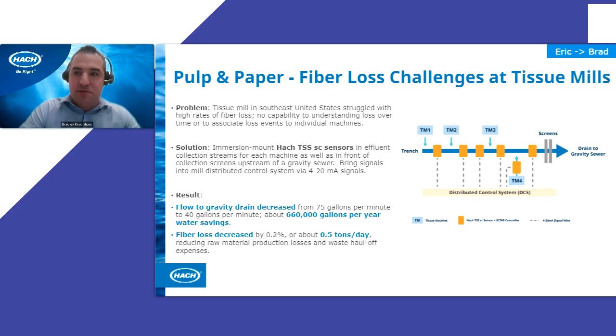The Hach solution was to install TSS SC probes with the wiper in an immersion mount fashion at points on the effluent side of each tissue machine, as well as directly upstream of the screen in front of the gravity drain. The mill brought those signals into their distributed control system via 4 to 20 analog signals and implemented optimization strategies for each tissue machine based on analysis of peaks in TSS measurements.